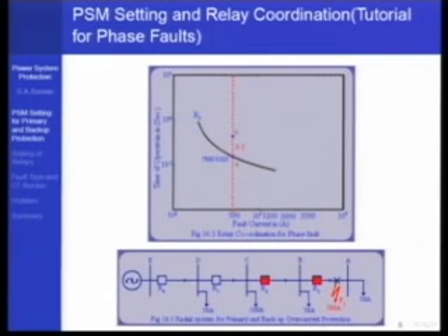So now I know the minimum operating time of the relay R2. It can be slower than this, but I don't want to make it any slower. Why unnecessarily slow down the protection system? So I have determined the operating time of the relay R2. Now for relay R2, you have seen the standard IEC equations or the ANSI equations. Once you have picked the characteristic, you know the equation. The left hand side is T, the operating time of the relay. That value you know. Pickup value you know. Once you know both these values, there is only one unknown, which is TMS. So you will calculate the TMS value.